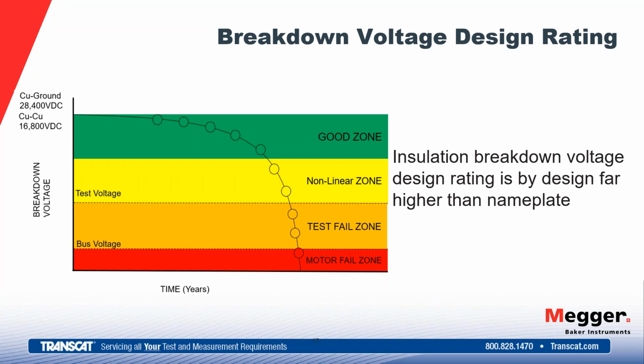Thus preserving the option to continue operating the motor. So again, if the insulation is degraded, high voltage testing may take away up to one startup cycle. Again, realize that this high pot testing is at much lower energy than when you hit the start button. If the insulation is good, it will withstand that and report back to you a good insulation system. Whereas if it's weak, then we're reporting back to you that you have a less than reliable motor in your service.